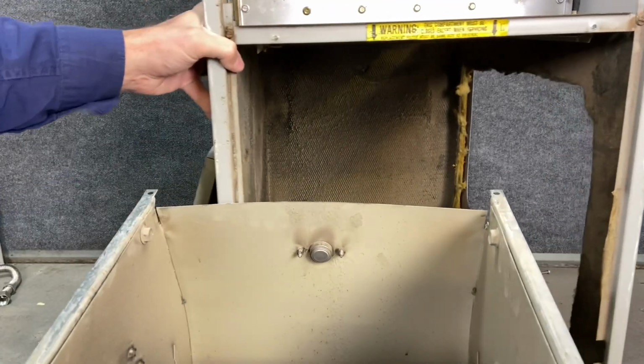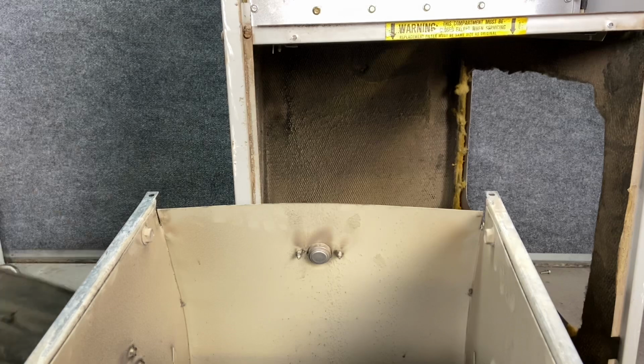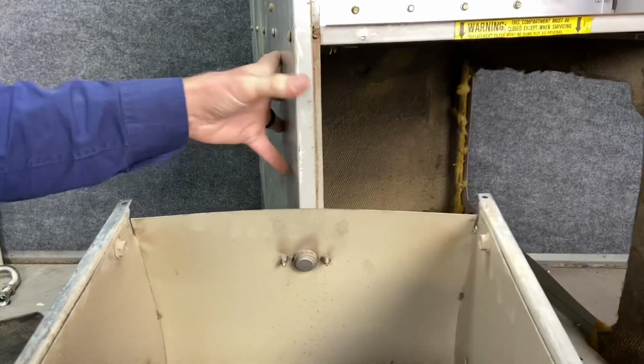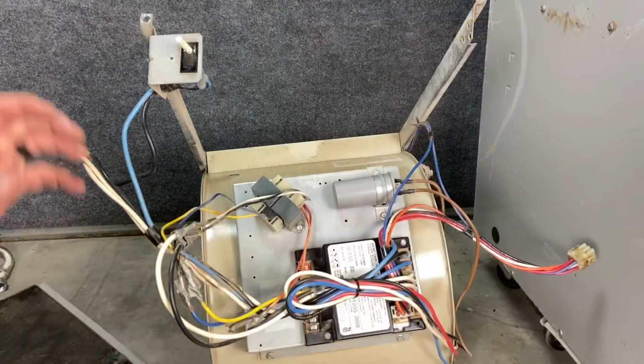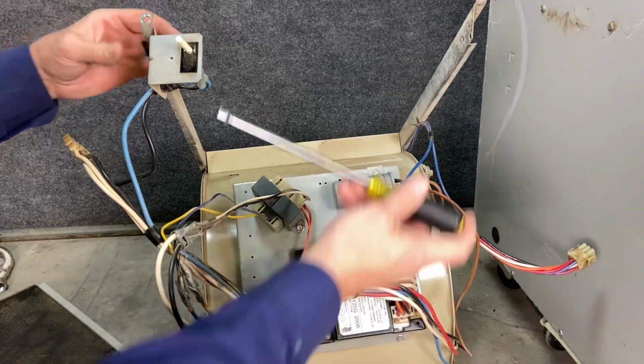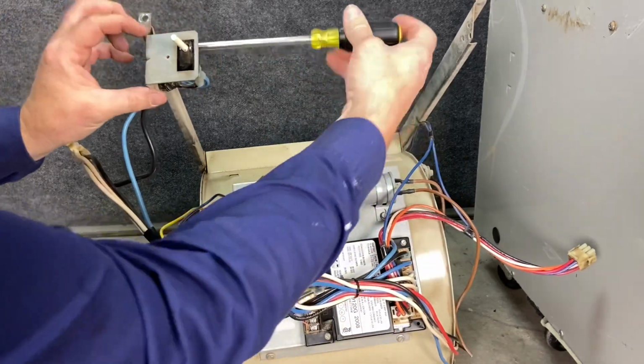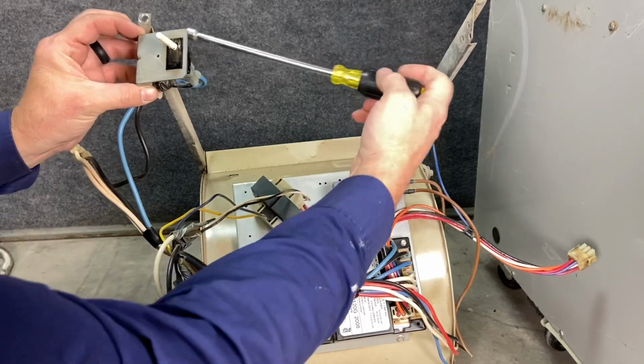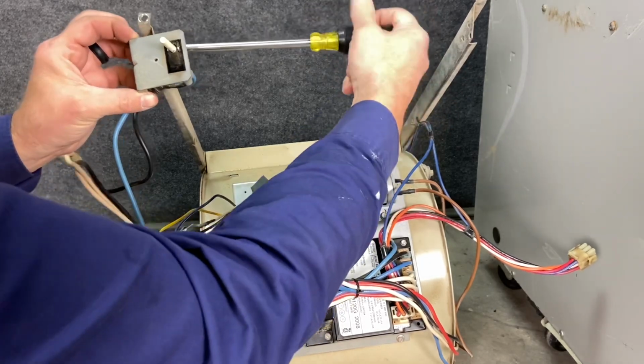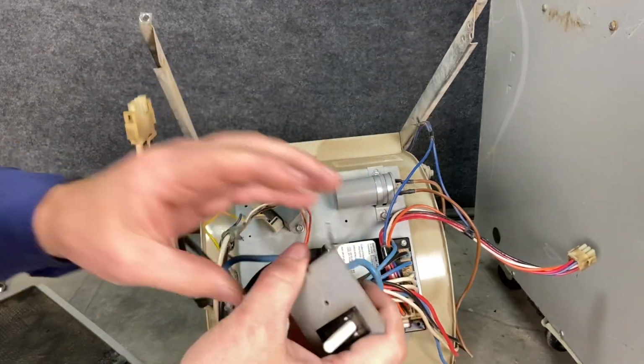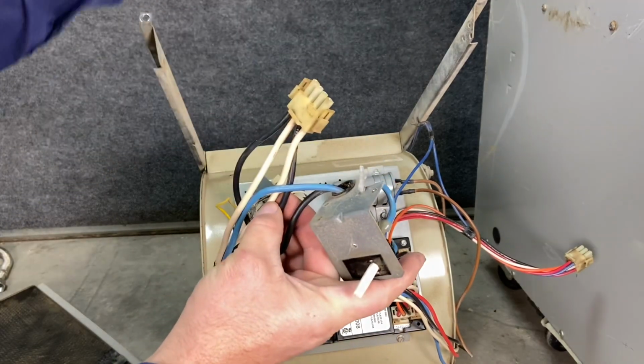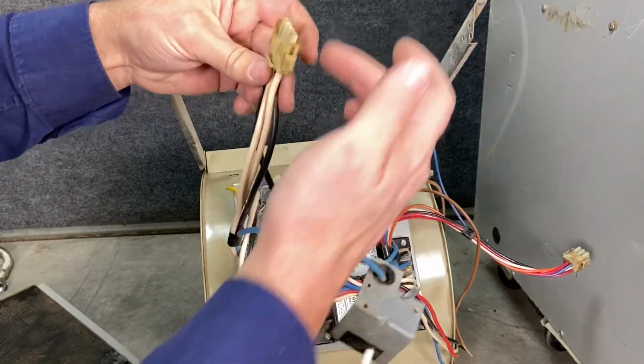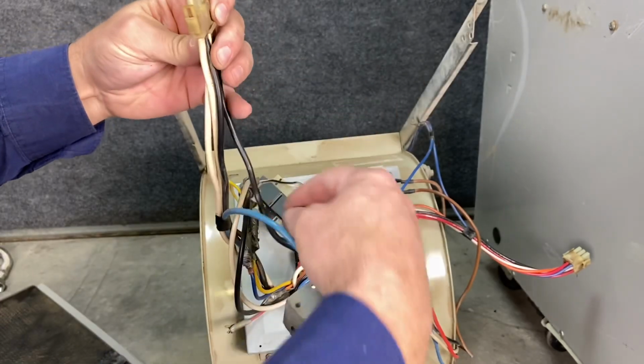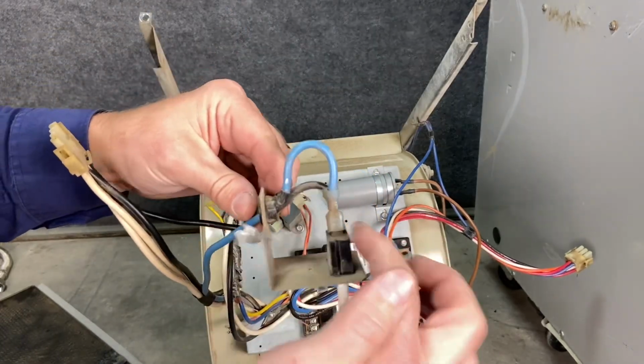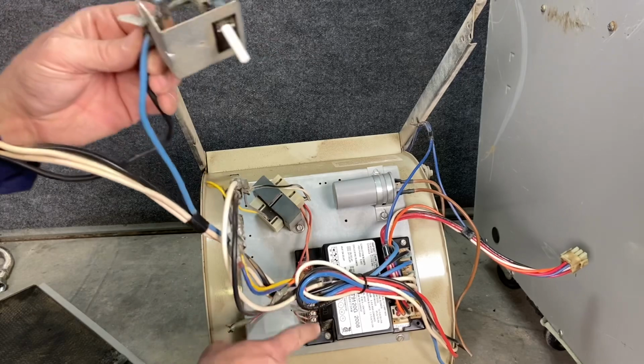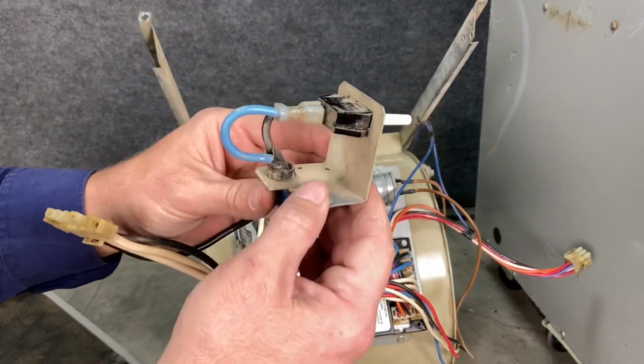We're going to push the furnace out of the way, which is a luxury we don't get to do in the field. So we have this furnace out where we can see all the components. I'm going to start with the door safety switch, or door interlock, so we can get a better look at it. Two screws, this comes off, and all the power, the wires coming in from up top, the hot wire comes from the pigtail down into the switch, out of the switch, and then it goes to the control board to power everything else. But this is our door safety switch.